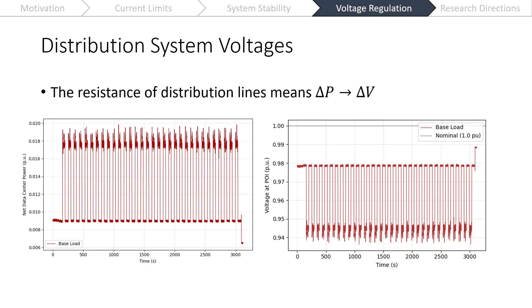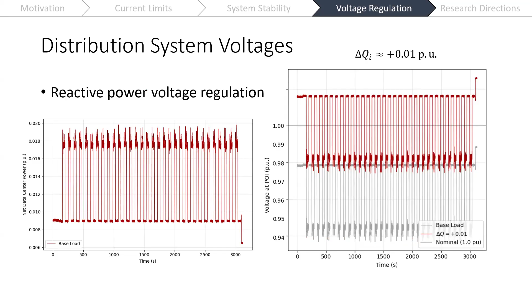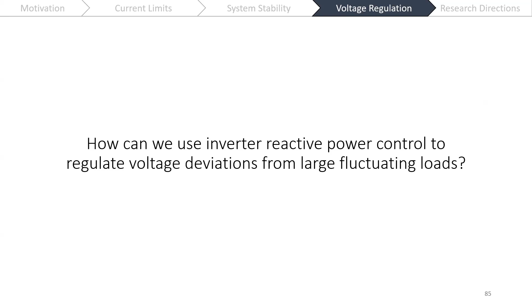Looking at how reactive power could help in this case, maybe we just want to shift this up. If we increase or inject reactive power at that data center bus, we're going to be more centered around our nominal voltage, but we're still going to have these large spikes here, which we'll talk about a little bit later on. So the first question we ask is, how can we use inverters' reactive power control to regulate voltage deviations from these large fluctuating loads?